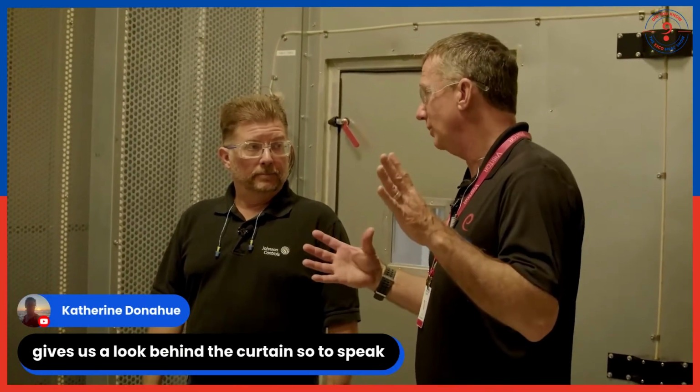Behind me, you'll see several layers of perforated sheet metal. Those are settling screens. Their purpose is to make the airflow as uniform as possible so we can get accurate static pressure measurements. Absolutely. In any ductwork scenario, we know that an open plenum is going to have a variance of air distribution and air disturbance, based on the construction of it. So you're softening and dampering that entire airflow to get consistent measuring through the entire chamber. Correct. Wow. Okay. Very interesting. Cool. Thank you.